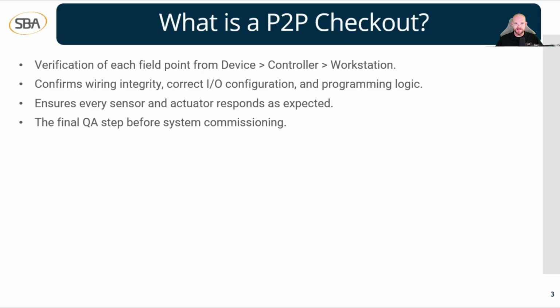The big idea to remember is that there's a difference between point-to-point checkout and the installation side. When we get to the point-to-point checkout, we are already past the installation side of things. We've already installed our sensors, our software, and any output devices that we might have. All of this has already been done, so we're past the installation part and now into the checkout part. We're checking these devices that we've already installed for operation.